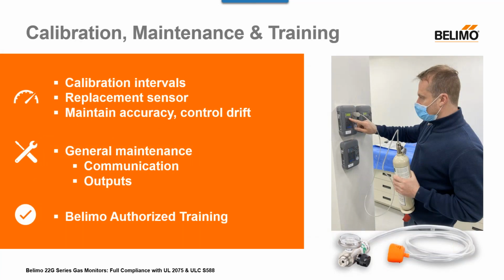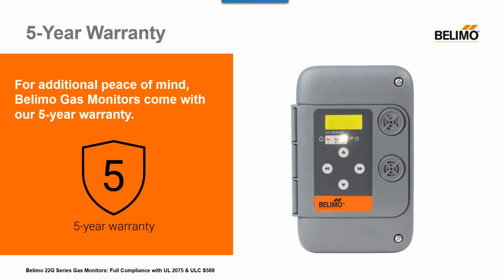To ensure accuracy, manufacturer recommendations call for gas monitor sensor modules to be calibrated every 12 months, or even more frequently depending on the application. Belimo sensor modules can be recalibrated in the field, or for added convenience, field replaceable sensor modules are available, allowing for a quick swap out without the need for on-site calibration. We recommend general maintenance checks to ensure the right power supply, configuration, and outputs are controlling the fans or dampers, as well as any communication between devices. Please look out for our new Belimo authorized training program, which takes a deep dive through the design, installation, troubleshooting, maintenance, and calibration recommendations. And like all Belimo products, they have the Belimo 5-year warranty, with one exception, the sensor modules that carry the 1-year warranty.